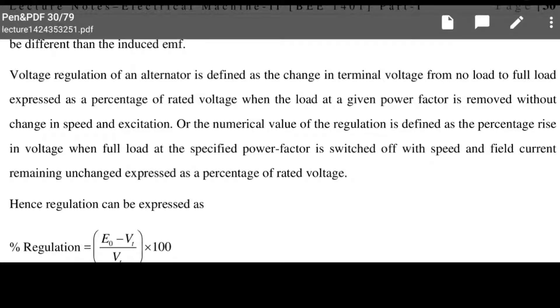The voltage regulation of an alternator is defined as the change in terminal voltage from no load to full load, expressed as a percentage of rated voltage, when the load at a given power factor is removed without change in speed and excitation. That is very important — speed and excitation must remain constant. The field excitation voltage and speed should be maintained constant to find the voltage regulation.